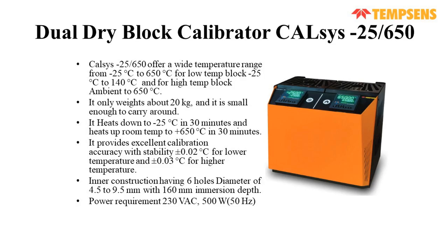Then we have the dual dry block calibrator. The range is minus 25 to 650, and it has 2 blocks in a single body. So you can expect a wide temperature range from negative to a medium temperature like 650. It has minus 25 to 650 in a single body, with one block going from minus 25 to 140 and another from ambient to 650. It just weighs 20 kgs, and it is small enough to carry for field applications, and you can use it for laboratory applications as well.